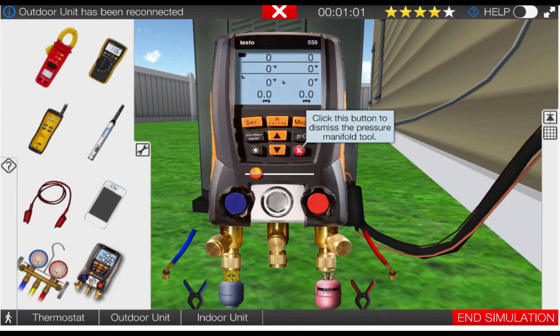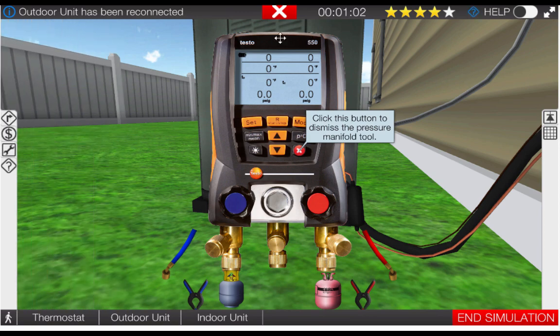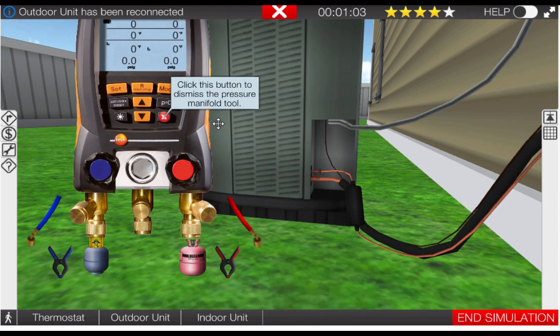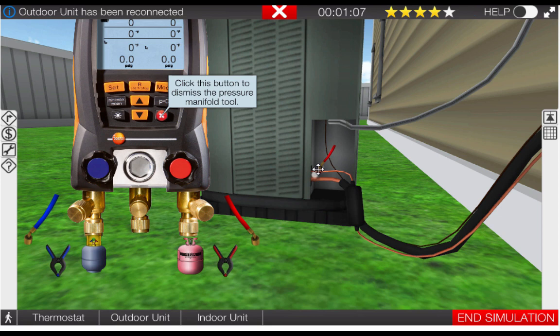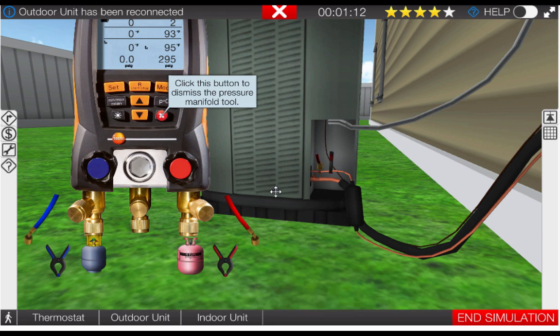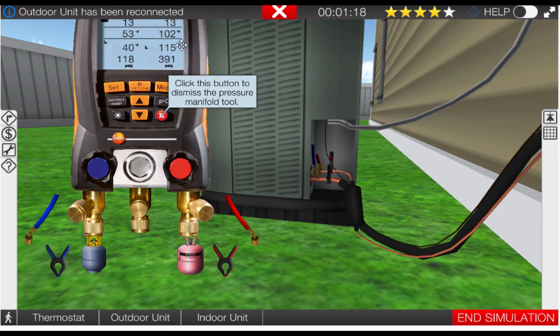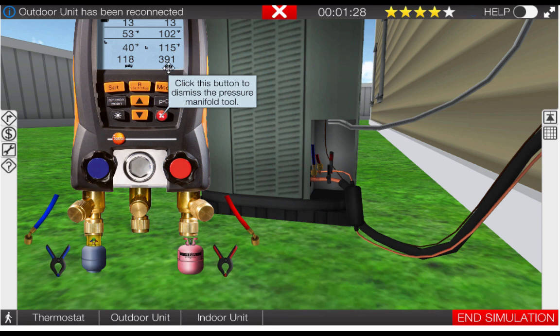Take the digital gauge manifold out of the toolbox. Place the red hose on the liquid line service port and the blue hose on the suction service port. As we can see now our condensing temperature of 115 degrees from the 391 psig corresponds to a temperature 20 degrees above ambient which is normal. Our suction pressure of 118 psig results in an evaporating temperature of 40 degrees. This is also a normal operating condition.